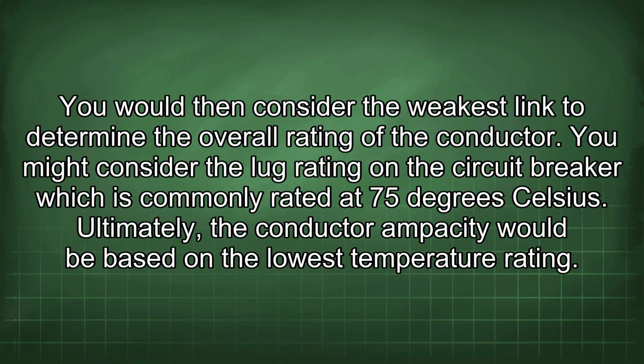You would then consider the weakest link to determine the overall rating of the conductor. You might consider the lug rating on the circuit breaker, which is commonly rated at 75 degrees Celsius. Ultimately, the conductor ampacity would be based on the lowest temperature rating.